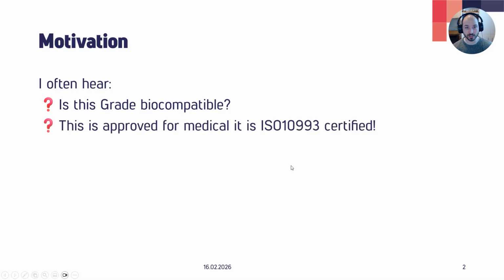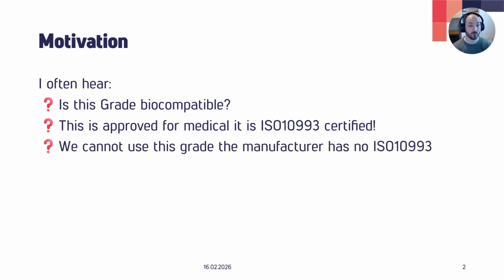How do we incorporate biocompatibility early in the plastic recommendation phase? This is one of the most frequently asked questions because I often hear, is this grade biocompatible? Or this grade is approved for medical since it is ISO 10993 certified. Or we cannot use this grade because the manufacturer has no ISO 10993. I would say all of this is half knowledge, because ISO 10993 doesn't mean approved for medical. And we will myth bust a little bit how biocompatibility actually works.